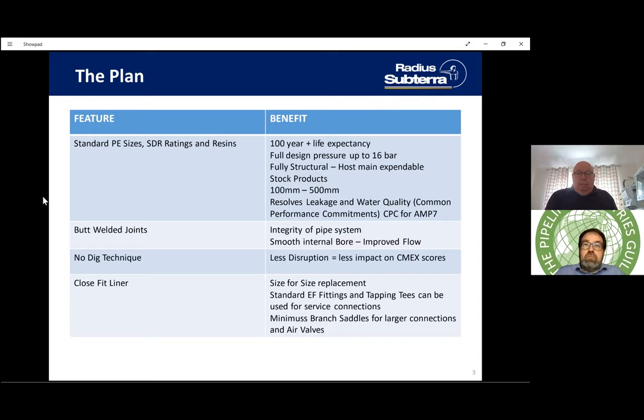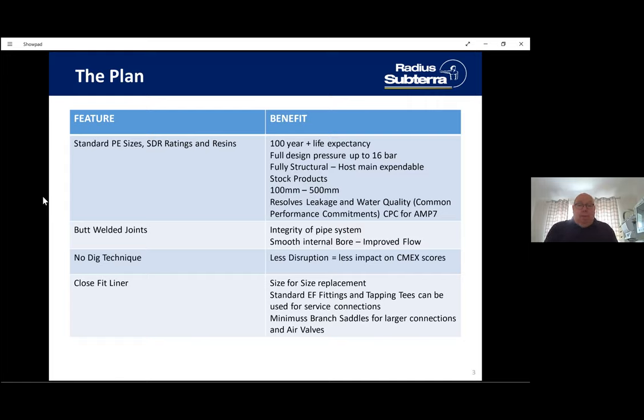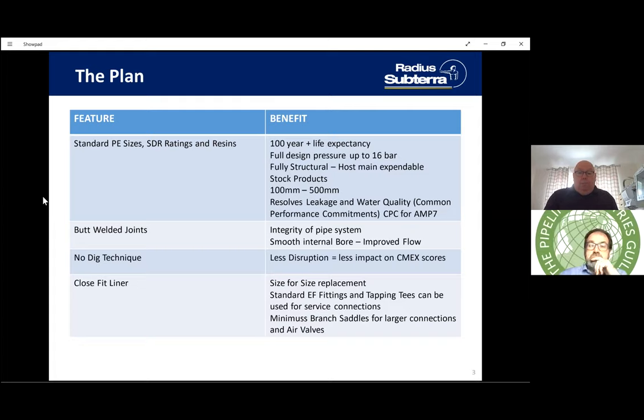Butt-welded joints mean the integrity of the pipe system is without question. Smooth internal bore gives improved flow. It is a no-dig technique so there's less disruption, which will impact your CMEX scores — those now include not just water delivery but also roadworks environment that customers can complain about. It is a close-fit, size-for-size liner. Standard electrofusion fittings and range-rated tapping tees can be used for service connections, and larger connections use our Minimuss Branch Saddles.